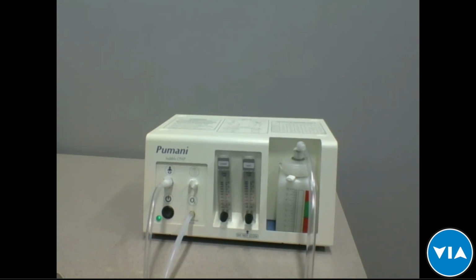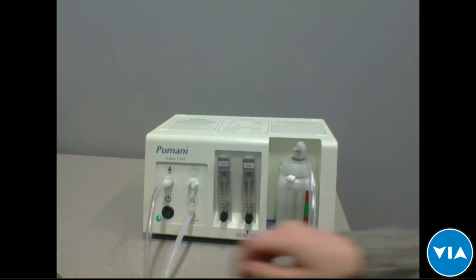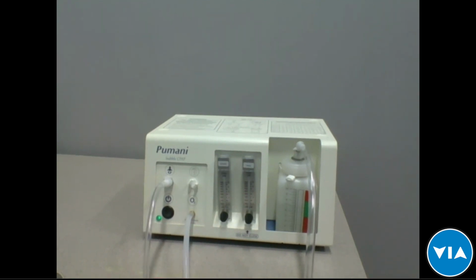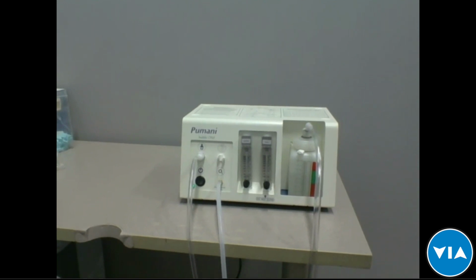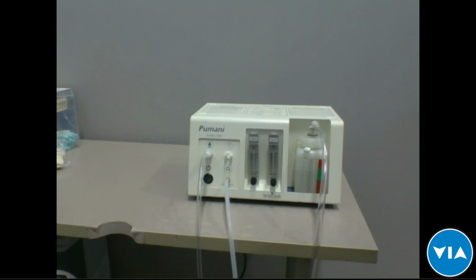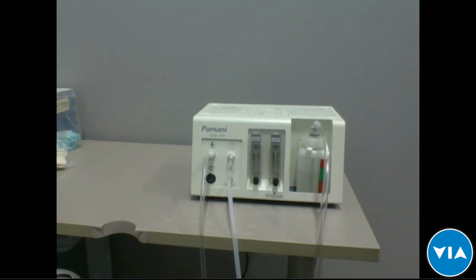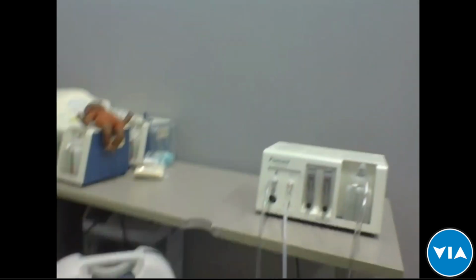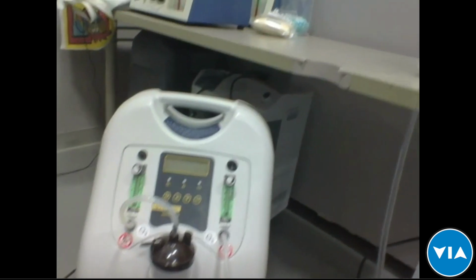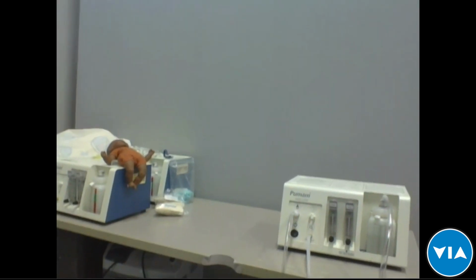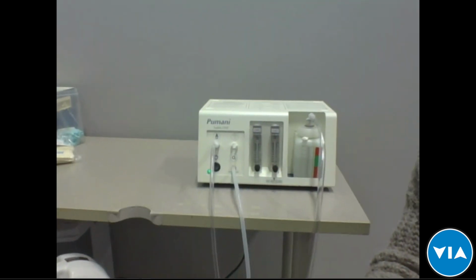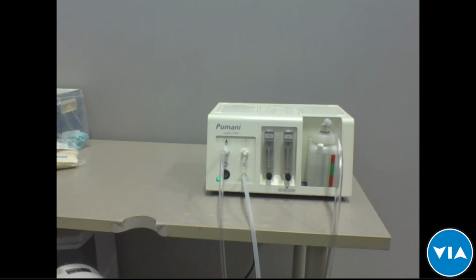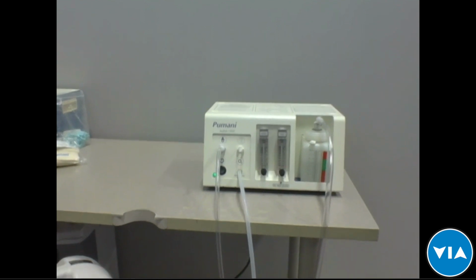And then you can now select your external oxygen source. In terms of external oxygen source to blend with the air, which is inside the Pumani, you can use a tank, you can use a concentrator, you can use walled air. It's compatible with any of those. But of course, the percentage of oxygen in your oxygen source will affect how much oxygen the baby is getting. So the Pumani assumes that you're using a concentrator or a tank with a lower level of oxygen. So it assumes about 94 to 95% oxygen is coming into the Pumani from the concentrator or tank, and then blending with the air made by the Pumani.